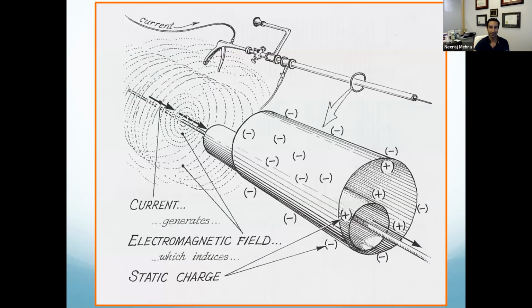Now, the other thing to be aware of, also how fires start in the OR, is this idea of capacitive coupling. This happens because when you have a metal wire, a metal conductor, passing electrical current, surrounded by an electromagnetic field, that creates a static charge. If you bring another electrical instrument to it, that generates a current.